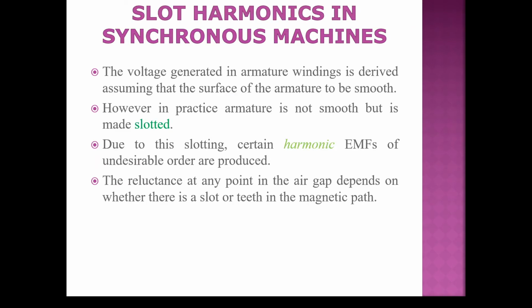Now let us see the slot harmonics. Voltage generated in armature winding is derived assuming that the surface of the armature is smooth. But in practice, when we see the actual armature, it is not smooth but slotted. Due to this slotting, certain harmonic EMFs of undesirable order are produced.